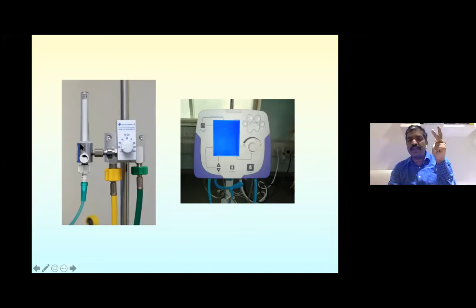So this is the pressure generator in bubble CPAP. In bubble CPAP, you are putting the expiratory limb. This is the expiratory limb which is going inside water, and how much is the depth from the water level? This tube is inside. Suppose from the water level, the tube is 5 centimeter inside. The pressure in the circuit is 5 centimeter. From the water level, if the tube is 6 centimeter inside, then the pressure is 6 centimeter inside the circuit, and that is the pressure which goes to the patient.